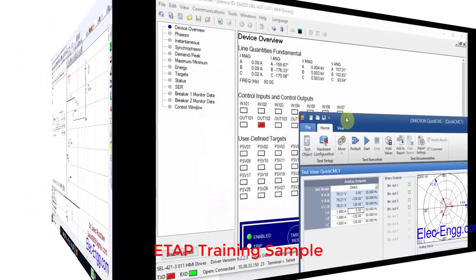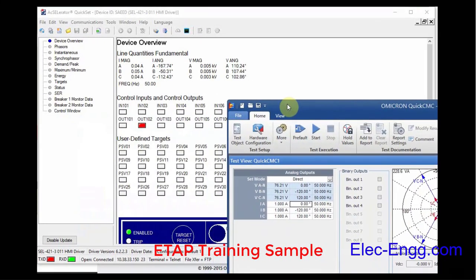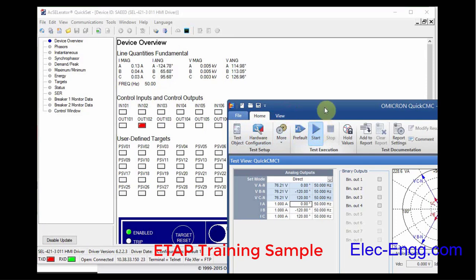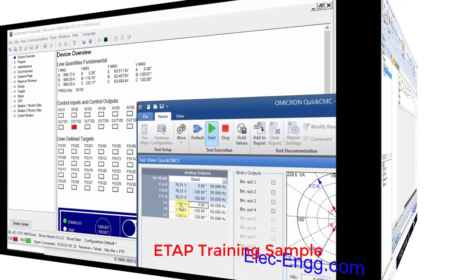We have to set minimum values so the functions do not pick up due to these noises. Now let's inject the three phase voltage and current to the relay. Here in the relay HMI, primary values are showing, and in the quick CMC module the secondary values are showing.